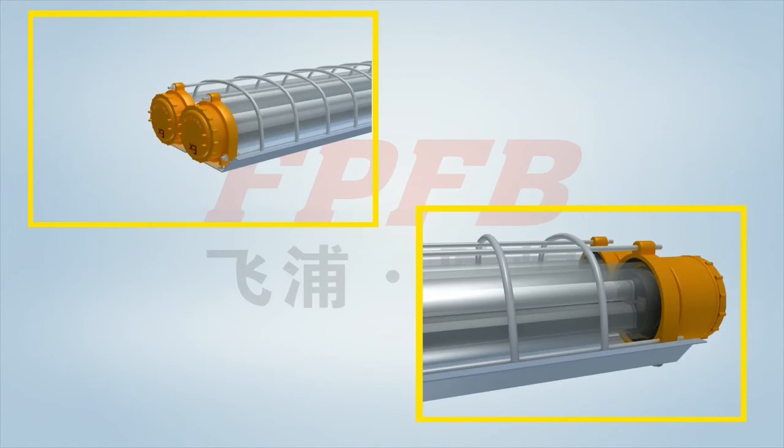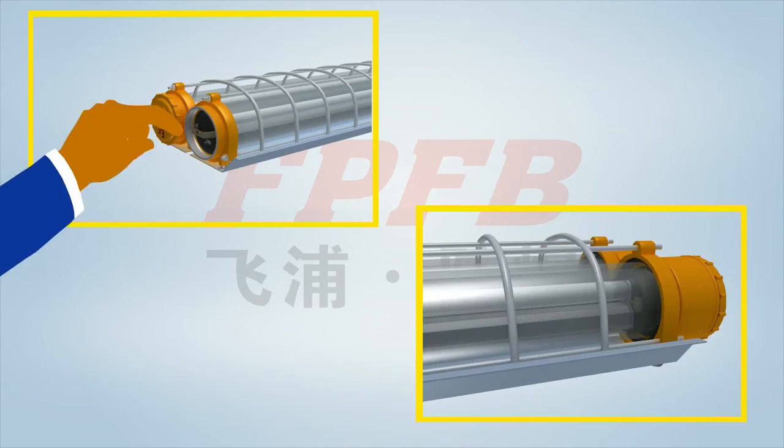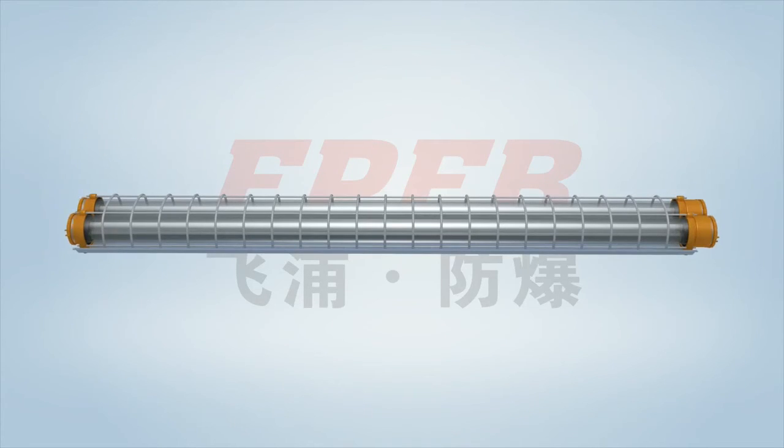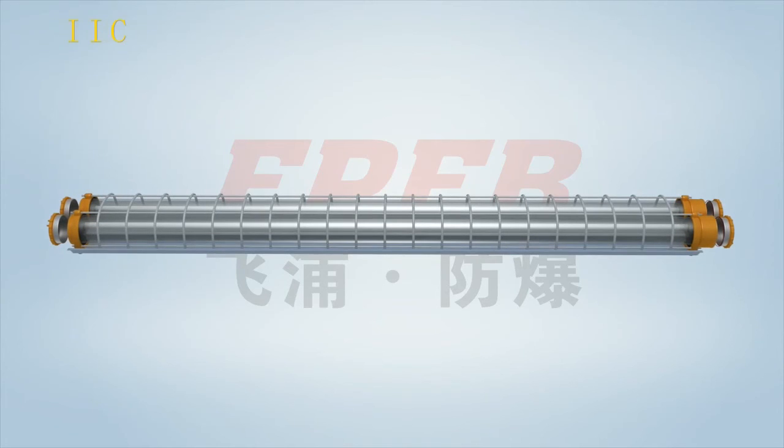To inspect, maintain, or change the light tube, just loosen the fixing holder and pull out the bracket of the light. The cabinets are firmly connected by screw thread, which is secure and reliable up to Ex rating IIC, IIB, and IIA.